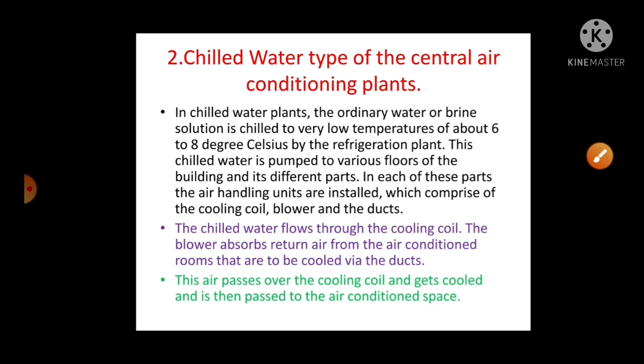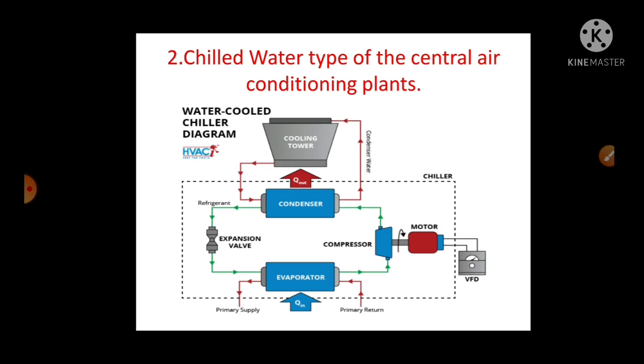Okay, now we will see the chilled water type central air conditioning plant. In a chilled water plant, ordinary water or brine solution is chilled to a very low temperature, about 6 to 8 degrees Celsius, by the refrigeration plant, and this chilled water is pumped to various floors. It is very easy to carry this chilled water to the required AHU located at different floors, and with the help of this chilled water we cool the air, and this cold air is supplied to each room on that floor. The AHU comprises the cooling coil, blower and ducts. The chilled water flows through the cooling coil. The blower draws return air from the air conditioned room that is to be cooled via the ducts. This air passes over the cooling coil and gets cooled and then is passed to the air conditioned space. And this is the arrangement of a chilled water type central air conditioning plant.